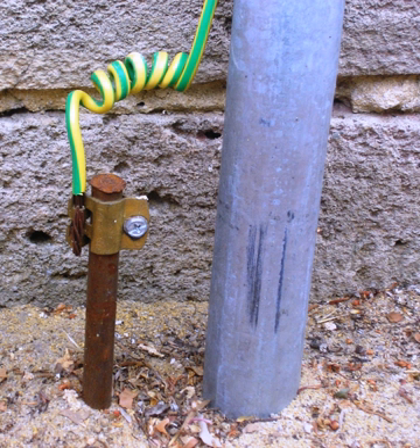To avoid accidents, such functional grounds are normally wired in white or cream cable, and not green or green, yellow. Topic: Separating low signal ground from a noisy ground. In television stations, recording studios, and other installations where signal quality is critical, a special signal ground known as a technical ground, or technical earth, special earth, and audio earth is often installed to prevent ground loops.